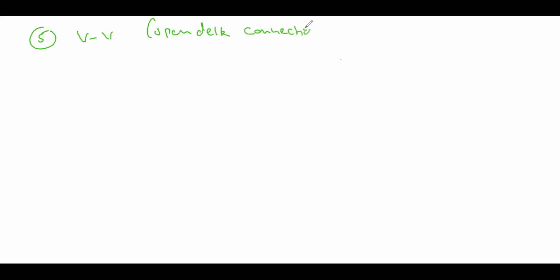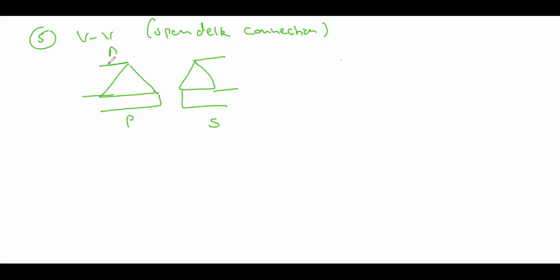Open delta connection means, in delta-delta connection, supply is given, this is primary and this is secondary. If one of the windings fails, say for example this is A, B, C and small a, b, c, the rest of the transformer will still work.